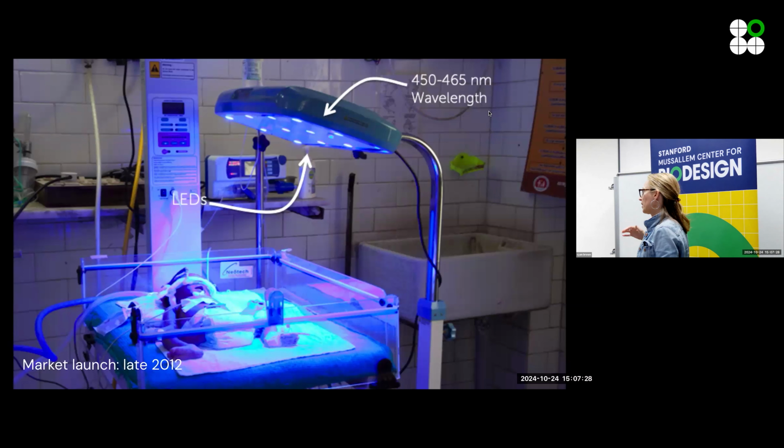And so the American Academy of Pediatrics has just updated their guidelines to blue LEDs. Some of you may remember that physicists won the Nobel Prize for blue LEDs, I think in 2016. So blue LED manufacturing was coming along and we were able to take advantage of that and get tightly binned blue LEDs. For the non-engineers in the room, what that means is, when you buy blue LEDs, they can guarantee a range, and as manufacturing got better, they can tighten it around your peak wavelength.